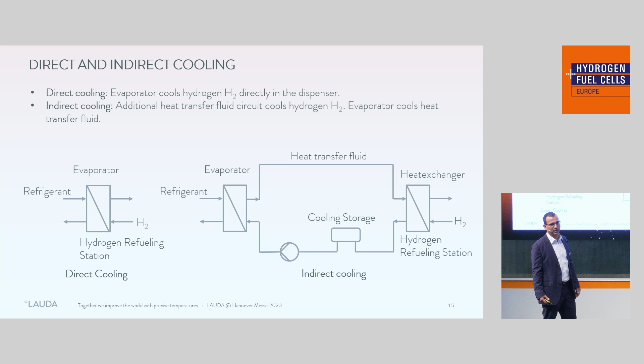What are the advantages and disadvantages? Direct cooling has fewer components and is a simple construction, as you saw in the picture, but it's a very sensitive system and only suitable for short distances. You also have to design the plant for peak power, so you need more or less double the energy.